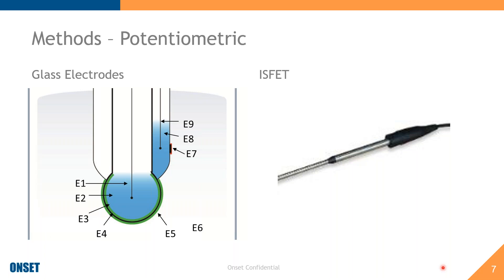A drawback with glass electrodes is that extended deployments will lead to measurement drift. This drift can be corrected by regular calibration with pH buffers. Some potentiometric pH systems use ion-selective field effect transistors, or ISFET, which provide great accuracy and precision for in-situ measurements. However, these require long conditioning periods ranging from a couple of days to six weeks before measurements become accurate. They are great for long-term deployments, such as monitoring ocean acidification over a long period, but are typically much higher in cost.